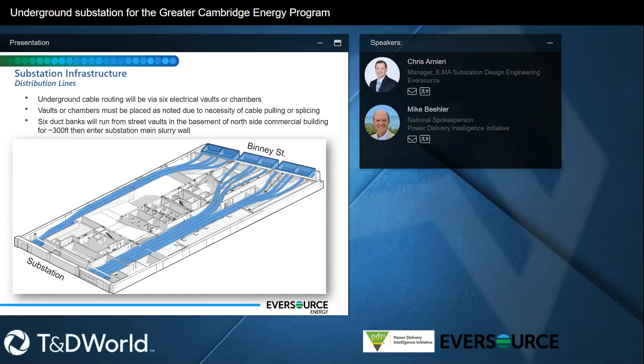One of the problems we had was being stuck at an elevation that was pretty high relative to the surface because of the parking garage, but our metal clad switchgear is all bottom entry, and we couldn't sink the switchgear low enough to accommodate a top entry. So as soon as those distribution circuits come in, we essentially bend them 90 degrees down into the floor below the metal clad switchgear, then route them back on themselves on racking systems to get them to the distribution feeder sections.